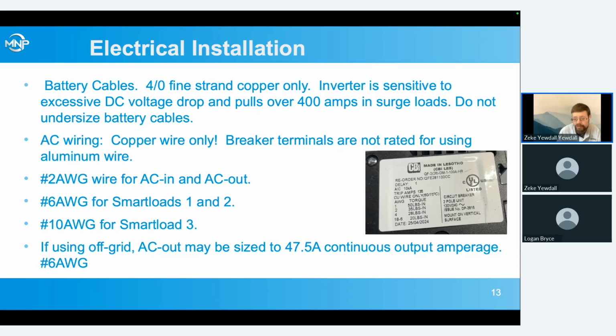In general, transformerless inverters are more sensitive than the old transformer-based ones, which wouldn't show you what they were doing. They would sag in voltage during surge loads, and it was pretty ugly looking at it on an oscilloscope sometimes, but they wouldn't shut off. The transformerless ones don't have that big giant block of copper in the transformer to help out with that. So they're more sensitive to voltage drop, and thus we really don't want to undersize the battery cables to them.